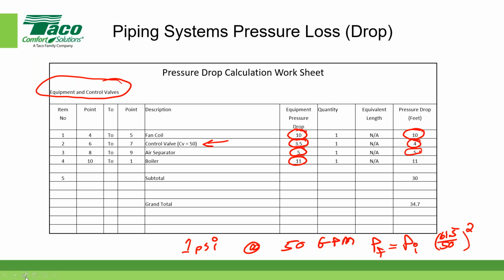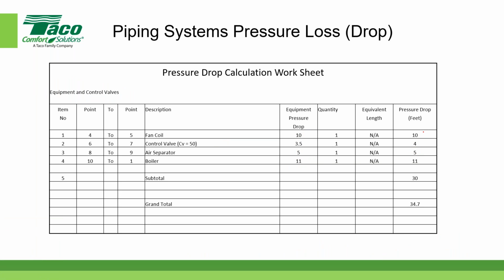Let me just erase the red lines here so it doesn't get confusing. So 10 and 4 is 14, 5 is 19, and let's see, that's 30. If I add all those numbers, they come up to 30. The grand total is 34.7, or roughly 35, because if you remember from the valves and fittings, pipe and fittings, it was around 5, it actually was 4.7. So the pressure drop for our little system here is 34.7 feet. Again, the pressure drop is in feet up here.